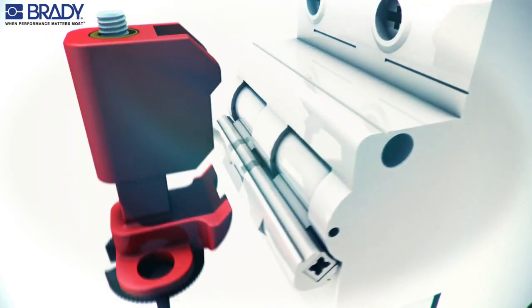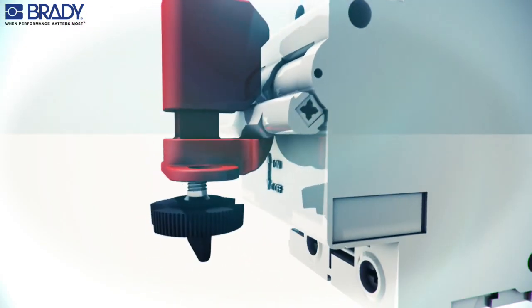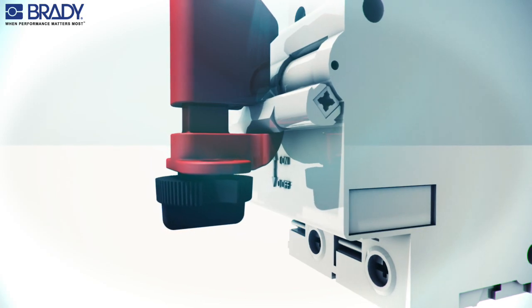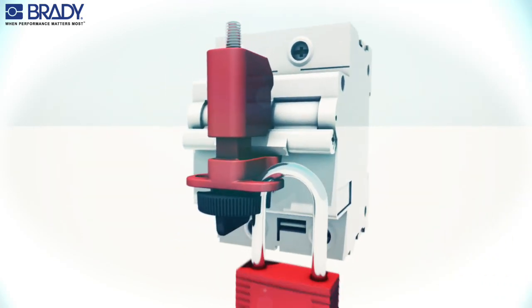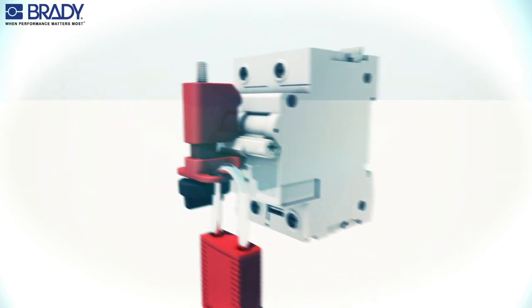Put the metal clip under the tie bar and between the poles. Rotate the thumb wheel clockwise to secure the lockout device to the circuit breaker, then insert the padlock through the hole to secure the device in the locked position.